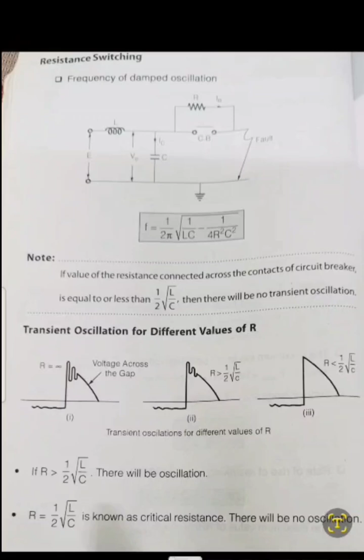Note: if the value of the resistance connected across the contacts of the circuit breaker is equal to or less than 1 by 2 root over L by C, then there will be no transient oscillation.